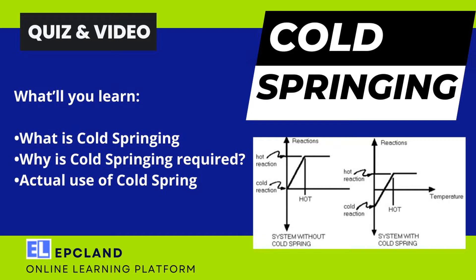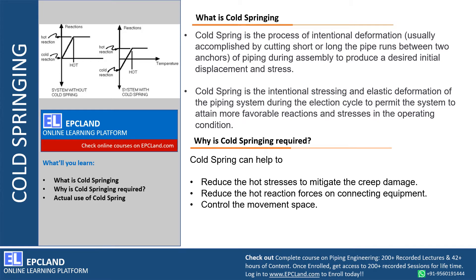Let us try to understand what is cold springing. Cold springing is a process of intentional deformation. What do we mean by intentional deformation? It is a deformation which we induce intentionally. When we are cutting the spools, we can keep them short or long. These short and long spools, which we intentionally induce, will cause the desired initial displacement.